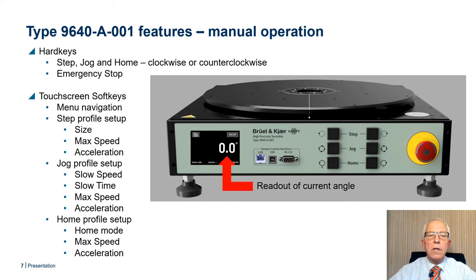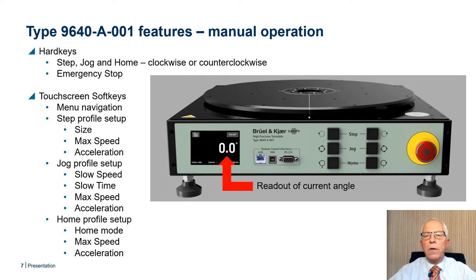Let us take a closer look at the front panel of the turntable. Here we find six hard keys for controlling the three main functions — step, jog, and home — supporting clockwise and counterclockwise rotation. We will also find the emergency stop that will halt rotation when activated. The touchscreen is located to the left on the front panel. This is where we find the soft keys for menu navigation and for setting up values for step, jog, and home profiles, as well as other relevant parameters. Of course, we will also find the readout of the current angle position in the display.